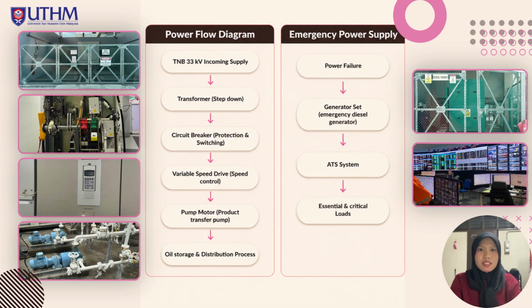As we can see, this diagram illustrates the overall power flow within the terminal. It starts with supply from the TNB 33 kV network, and at the end, during the utility supply interruption, the EDG automatically supply power to critical load.